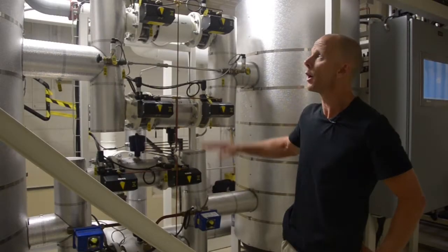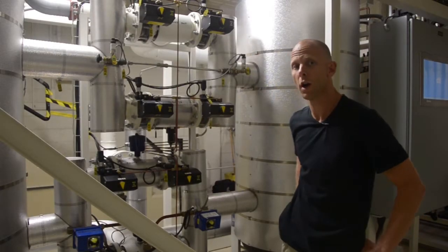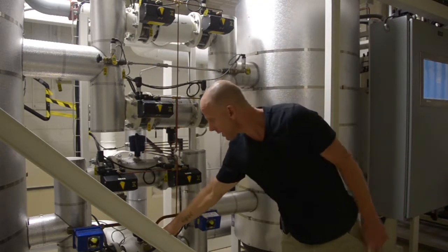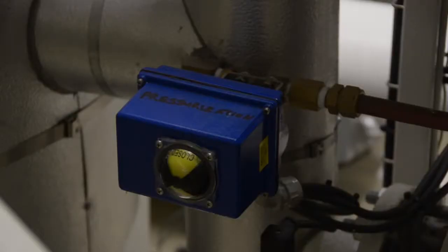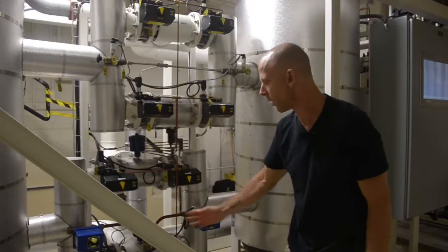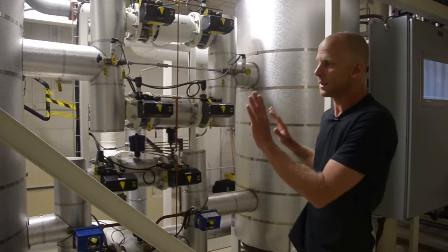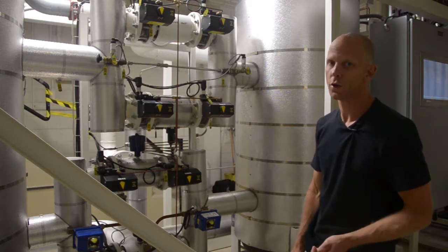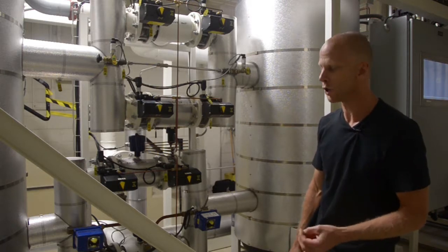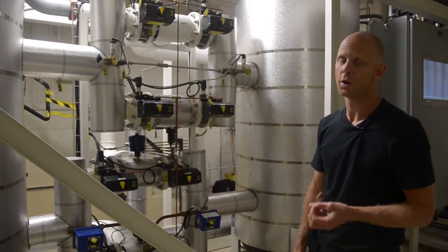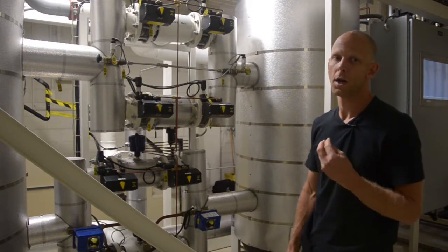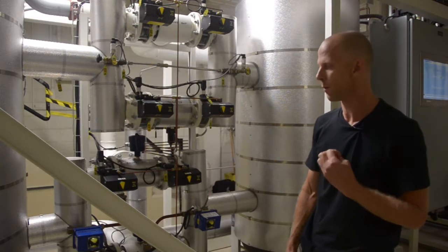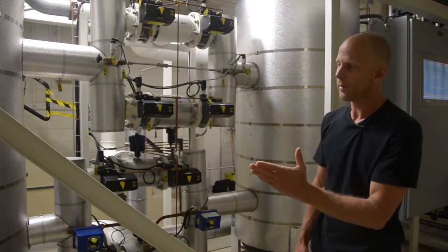Okay, so if we follow our process air through from our coalescer after the chiller, we'll find that our big air line comes down and into this line here, where we have two big valves. The air can go in either direction, either of one of two absorber beds. These absorber beds are basically molecular sieves, which will remove CO2 and water vapor from the process air stream. We want to remove both of those because both of those components will freeze at cryogenic temperatures inside our heat exchanger and cause blockage.